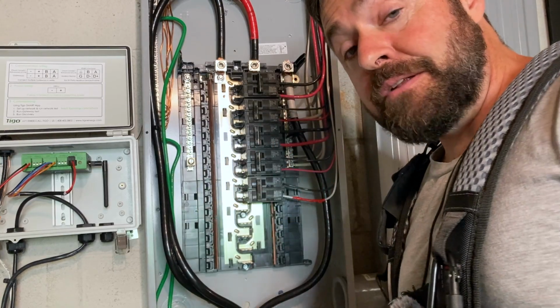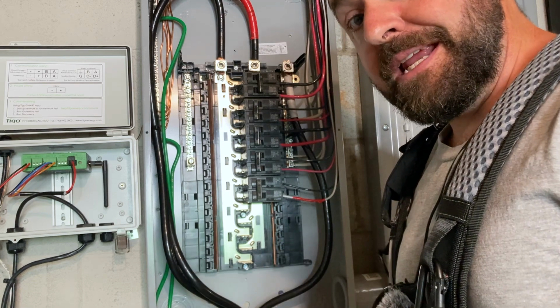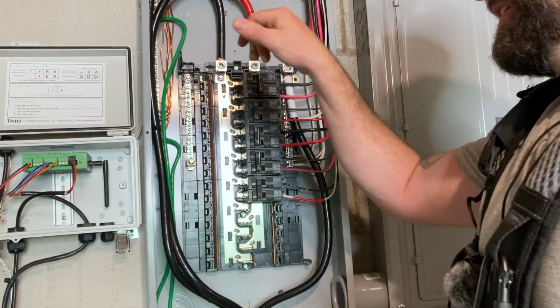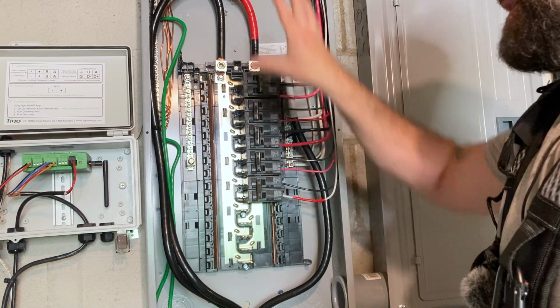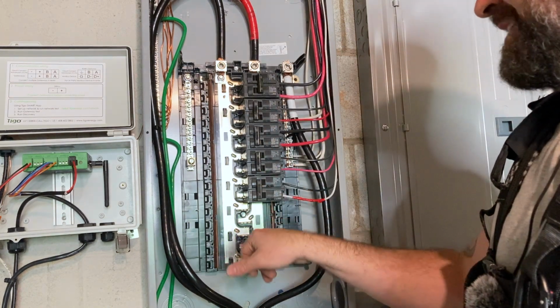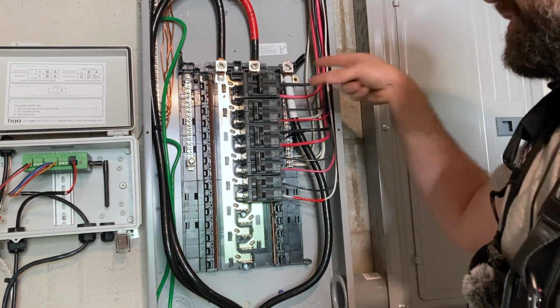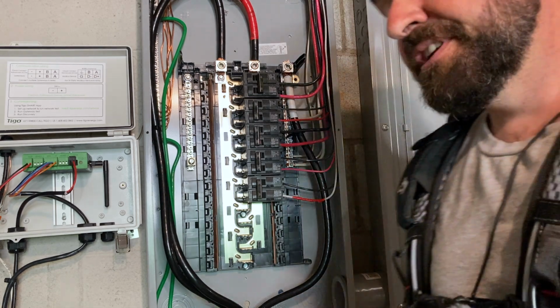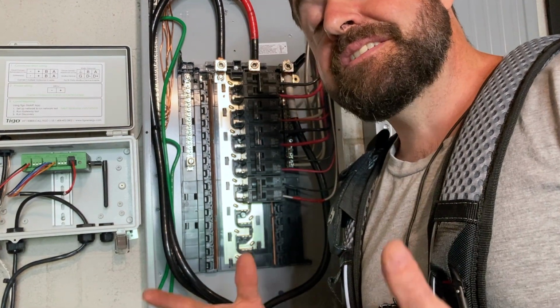Again, working in a live panel is extremely dangerous. I don't recommend anyone at home do it. If you touch anything exposed in here behind the dead front, such as that bus bar, the main lugs, or the terminals on these circuit breakers, it could be instantaneous death.